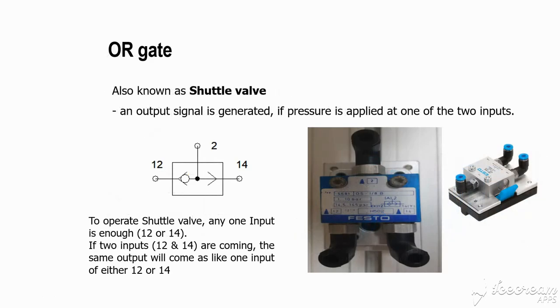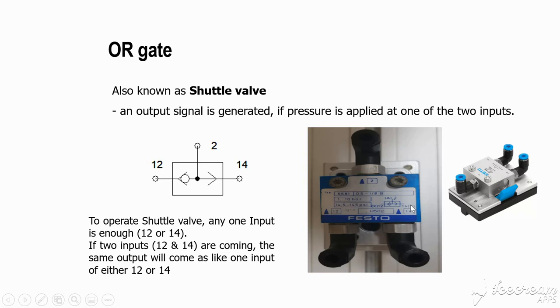The OR gate valve works on a different principle: any one signal is sufficient. When you apply air to either input, or to both, the air transfers to the outlet. Although the AND gate and OR gate valves look physically similar, they operate completely differently. A symbol is pasted on top of the valve so you can identify which type it is.